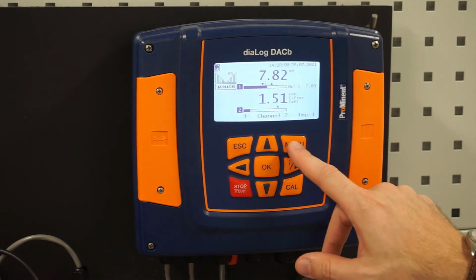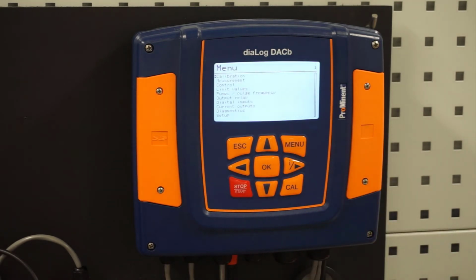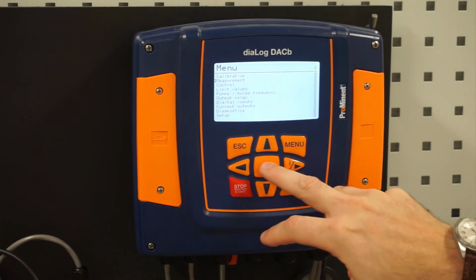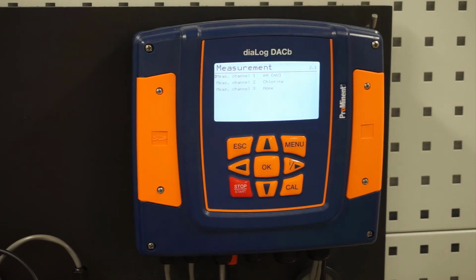I'm going to hit the menu button and we'll walk through each screen here. Most of this is set up for you from the factory if you buy it as a package. If you buy the controller separate and then the sensors and DGMA separate, you would be required to do all the programming. Calibration, we're going to skip by that, but that will be the last thing we do. The first screen after that we come to is measurement. This will be set up.